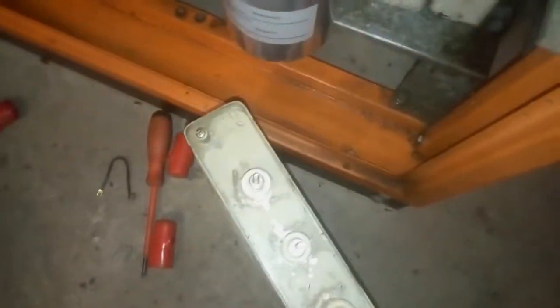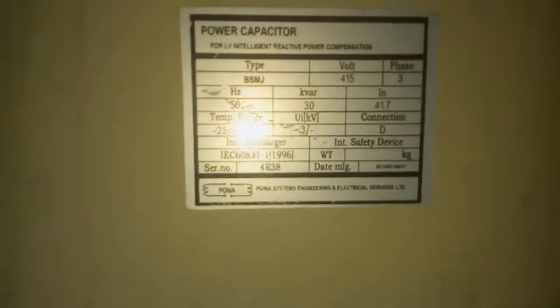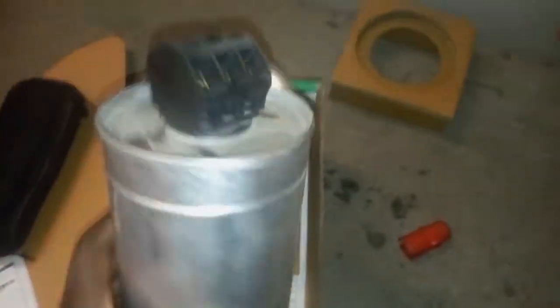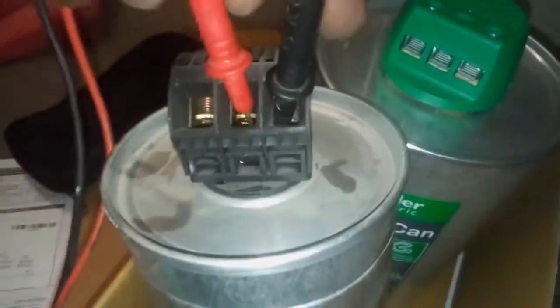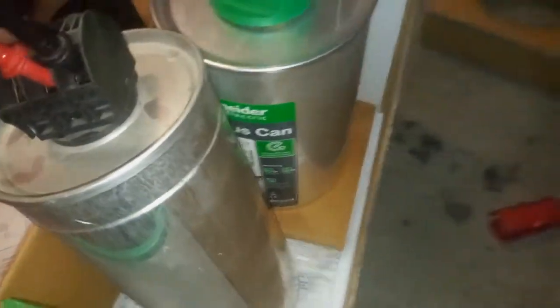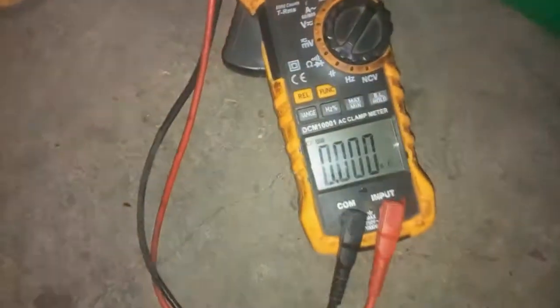I have removed two capacitors. This one is a 30 kVAR capacitor which is good, and another 30 kVAR which is bad. The bad one shows zero — no readings at all, no capacitance — so this is the faulty one we need to replace.